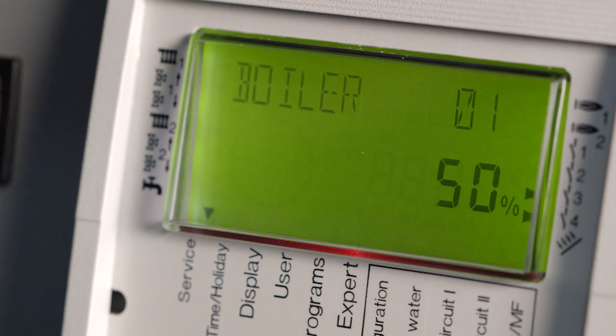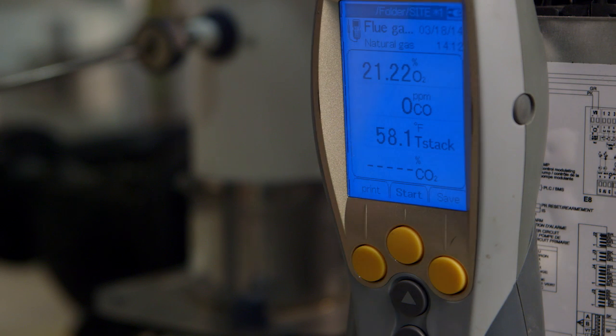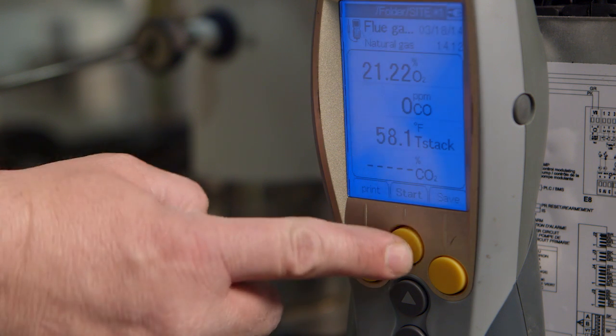Select Module 1 and set the fire rate to 100%. If your boiler does not ignite, that means your unit may have an ignition failure and requires an adjustment. If this occurs, consult your manual for ignition failure adjustment procedure. Now that this is done, turn on the pump to your combustion analyzer.